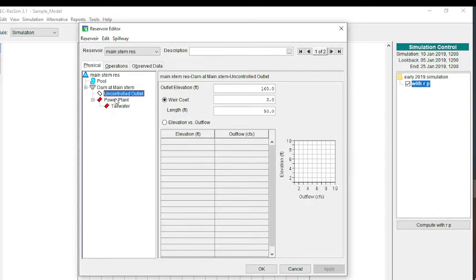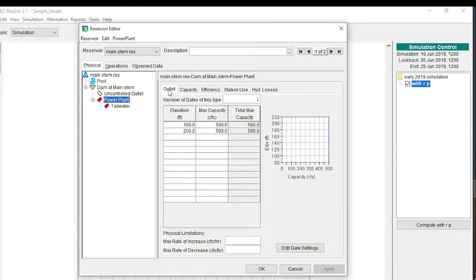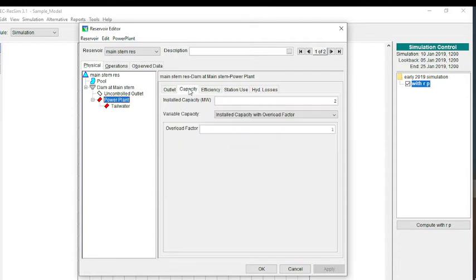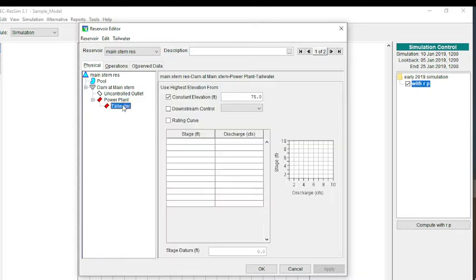The other outlet is a power plant. For the power plant, very simple parameters. I have a maximum flow capacity of 500 cubic feet per second, an installed capacity of 2 megawatts, efficiency of 80%. You do need a tailwater when you put in a power plant. In this case, I just made a constant elevation of 75 feet.